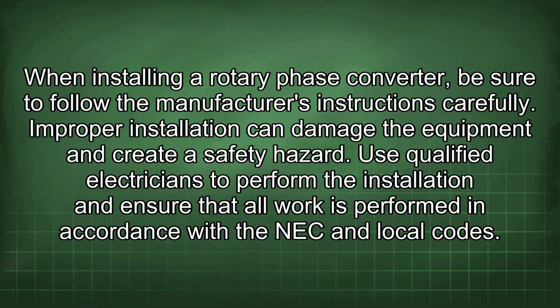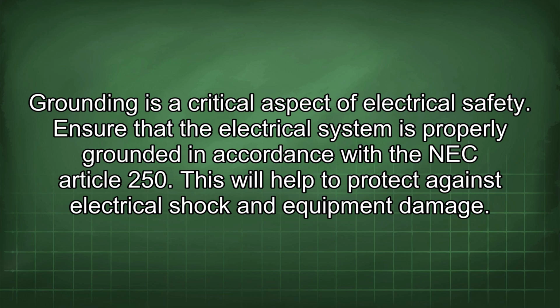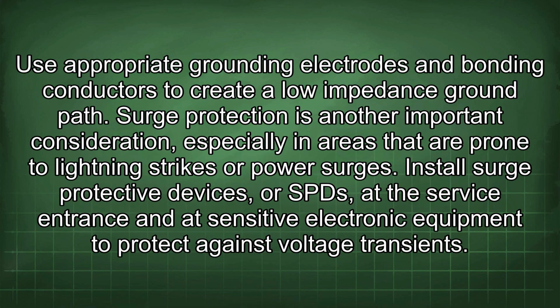Use qualified electricians to perform the installation and ensure that all work is performed in accordance with the NEC and local codes. Grounding is a critical aspect of electrical safety. Ensure that the electrical system is properly grounded in accordance with the NEC Article 250. This will help to protect against electrical shock and equipment damage. Use appropriate grounding electrodes and bonding conductors to create a low-impedance ground path.